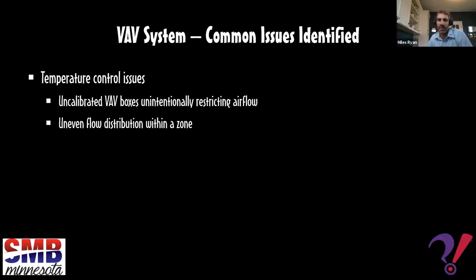So that is something where you could bring in a TAB contractor to help verify that the sensor has failed. Or if that had been done during the previous construction project, which wasn't too long ago in this particular building, maybe it would have been identified back then, if it's been an issue for that long.